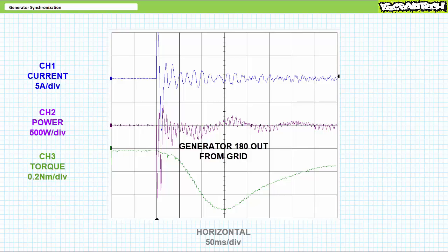The only time you ever close a contactor separating a generator from the grid is when the generator matches the phase sequence, phase shift, frequency, and voltage magnitude of the grid. That was fun. Let's wrap this lecture up with a quick discussion of how, once synchronized to the grid, a generator can meet the electrical power needs of grid-connected electrical loads. Once synchronized, ideally properly with minimal electrical and mechanical transients, a generator is essentially placed in parallel with the grid and is said to be floating, i.e. producing no power.